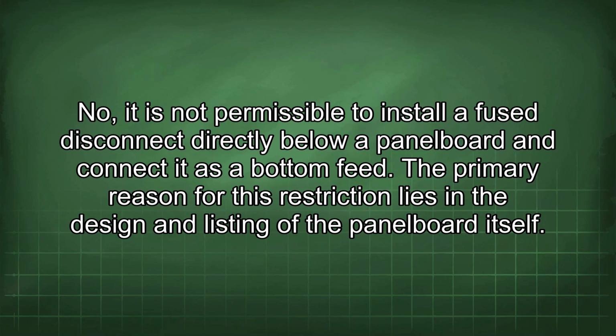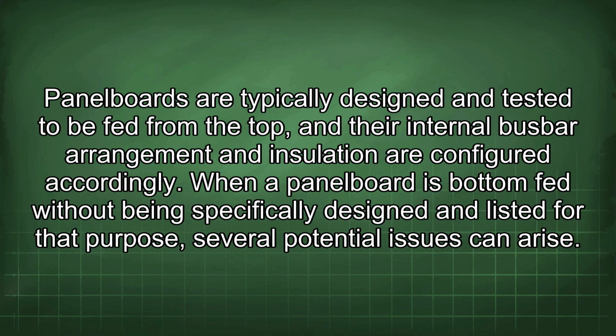It is not permissible to install a fused disconnect directly below a panel board and connect it as a bottom feed. The primary reason for this restriction lies in the design and listing of the panel board itself. Panelboards are typically designed and tested to be fed from the top, and their internal busbar arrangement and insulation are configured accordingly.